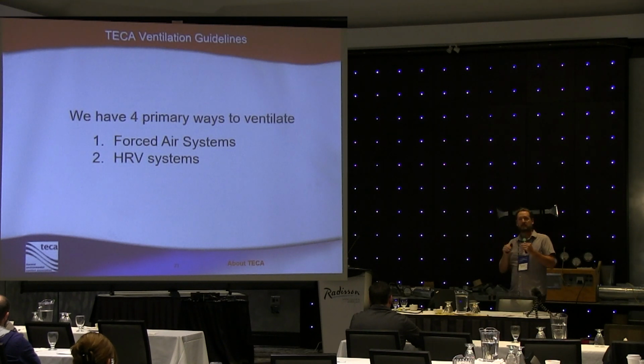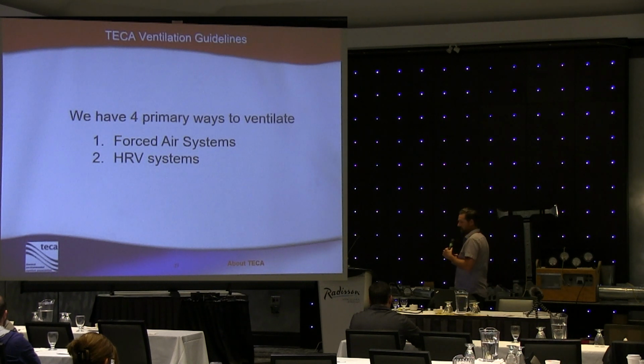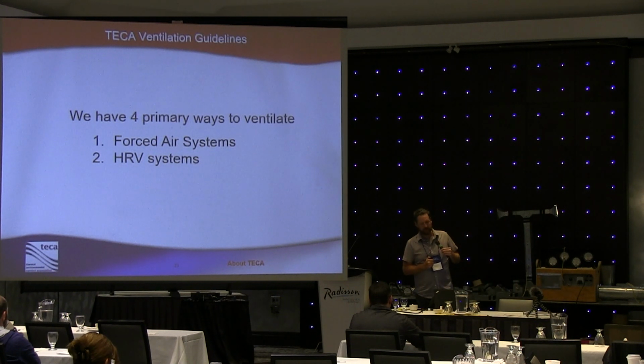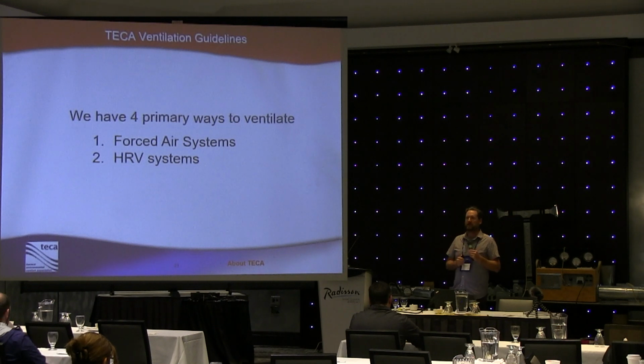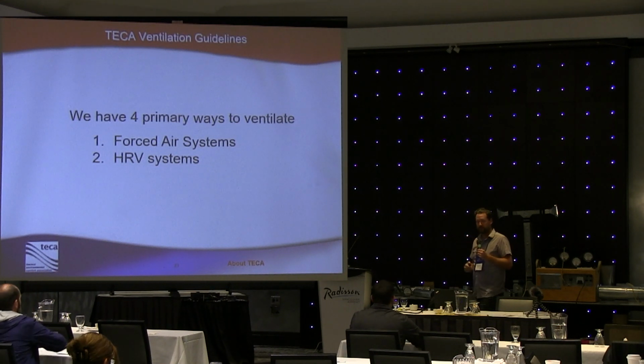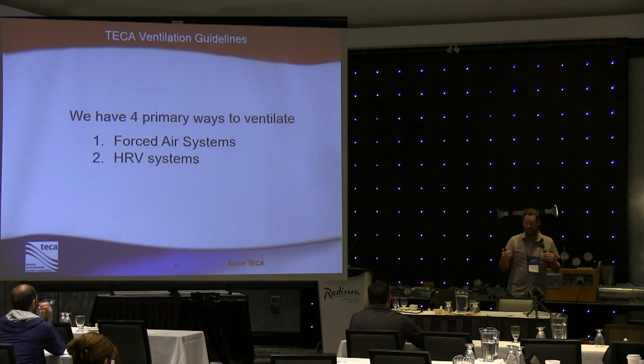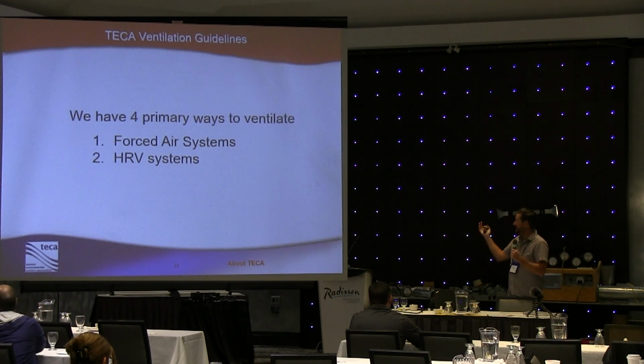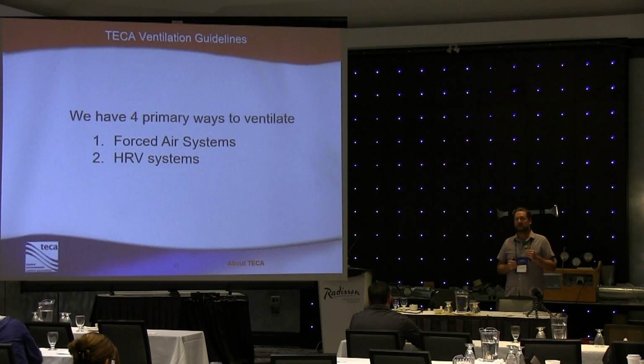It can be a system that is ducting fresh air out to all of the bedrooms independently, and has to exhaust from at least one point inside the building. A lot of installers will exhaust out of all the bathrooms. What they'll do is split that exhaust rate up and exhaust from the bathrooms. And the nice thing about doing that is when they exhaust from a bathroom, the HRV is going to run continuously, and you're going to be continually drying those bathrooms out. Works really, really well.